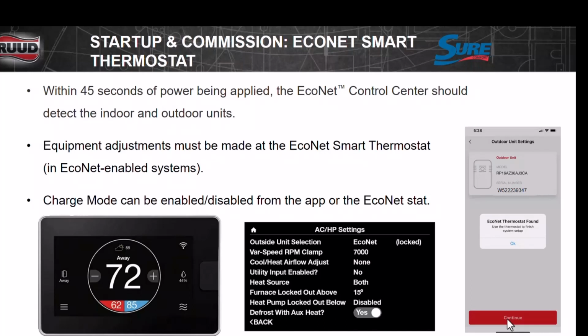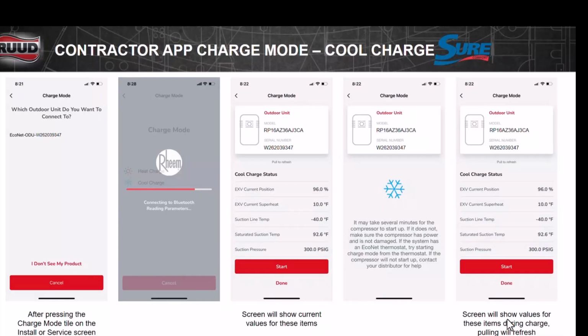The equipment adjustments can be made through the thermostat if you have an EcoNet thermostat on it. Bluetooth settings that you're going to be able to get into are going to be all diagnostic stuff. Okay? All the setup, if you have the EcoNet controller, is going to go through the thermostat. Whenever you log into the condenser, you can turn the condenser into charge mode. You see the RP16s here. On the outdoor unit, you open up the app on your phone, you go to diagnostics, you click charge mode, it turns it into charge mode. You no longer have to go to the thermostat to do that. And if you have the system that doesn't have the EcoNet controller, that's where you're going to turn it into charge mode on your phone too, because the indoor unit doesn't have that capability at that time.